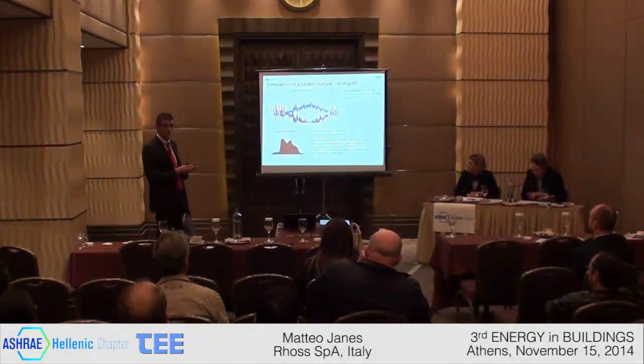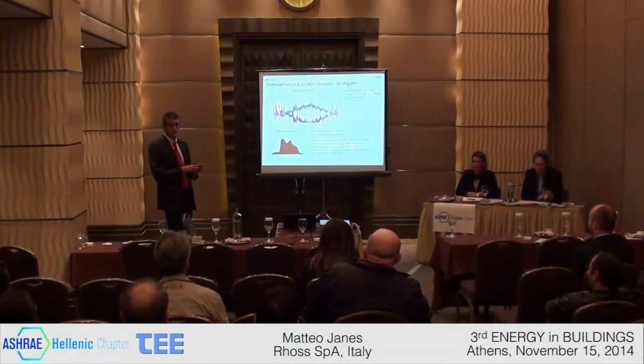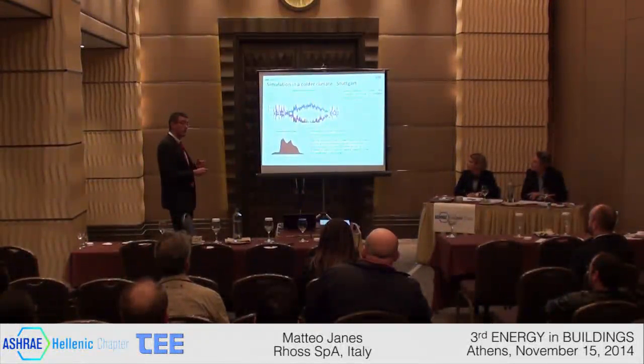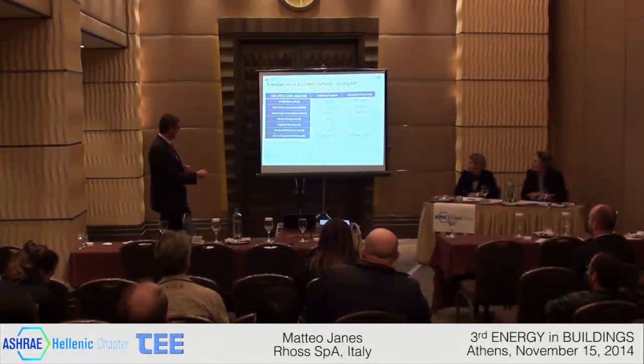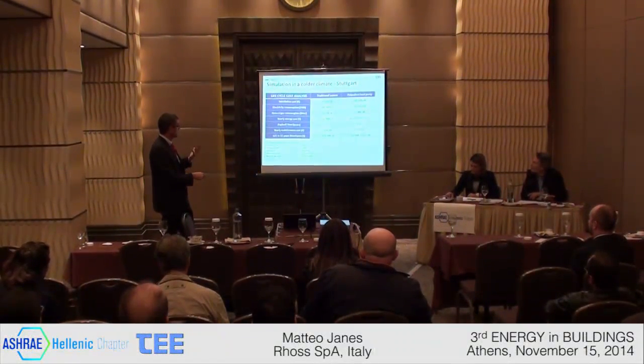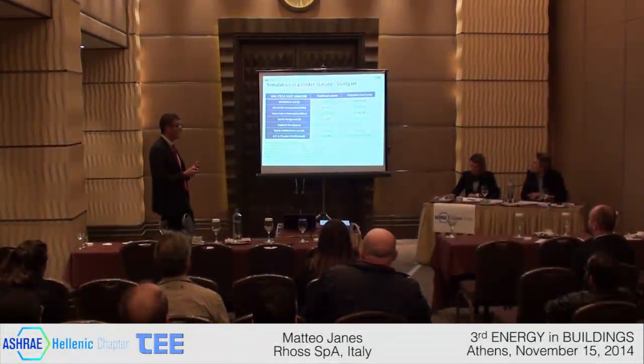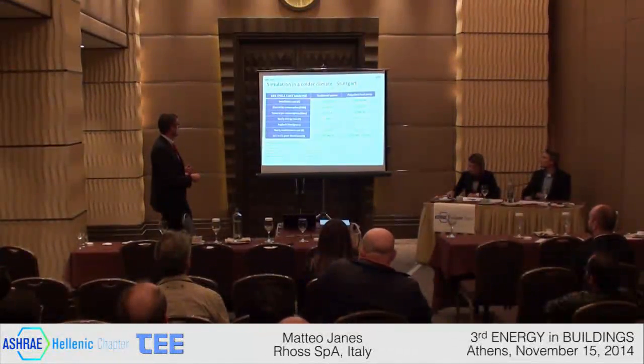With the gas and energy cost, the temperature at which the use of a heat pump was still convenient was calculated at -5. It means that when only heating is required below -5, the boiler is used and the heat pump is disabled. This is the simulation of a life cycle cost analysis for this situation. In this case, let's say the extra cost for the installation is even higher, because there is no saving allowed, because we have to use the boiler as well. So it exceeds a 50% increase.